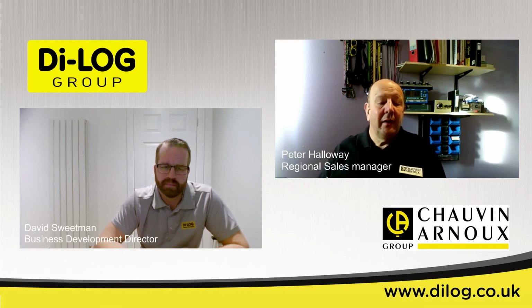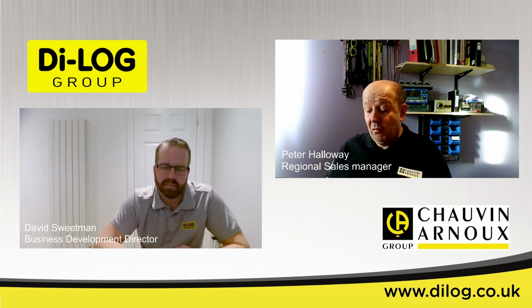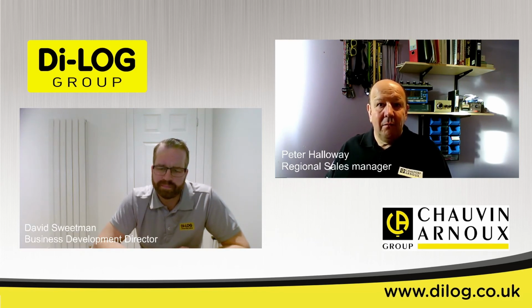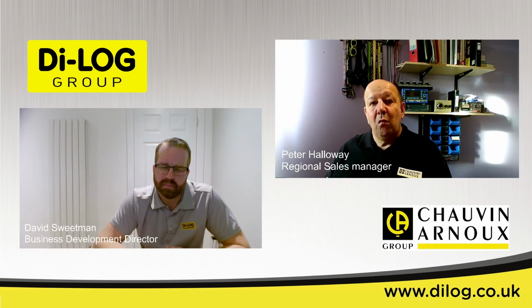So to answer your question, when it comes to the standards, total harmonic distortion is what's in the standard, with certain levels, 4 or 5%, depending on the harmonic. But when it comes to individual harmonics and looking at current harmonics, that's what we call the signature. An experienced power quality engineer will look at a waveform and say, that's got third and that's got fifth in it. They'll also know fifth harmonics, for instance, will be down to variable speed drives with 6 diodes in them, which will typically cause fifth and seventh harmonics. By capturing those individual harmonics, it gives you a clue as to where the problems are coming from and what you might need to put right.